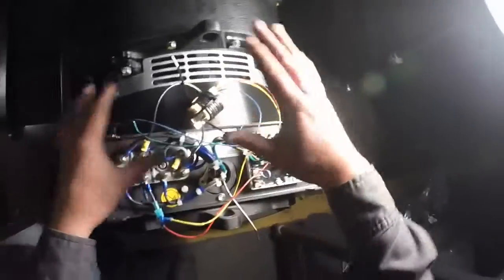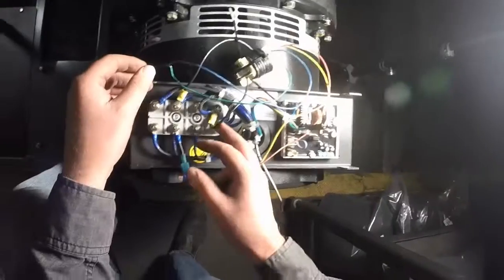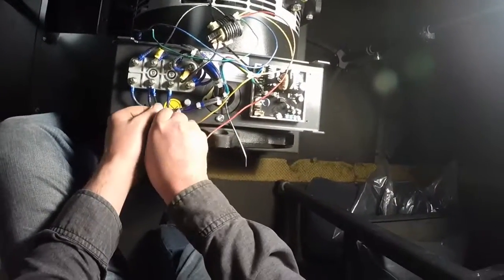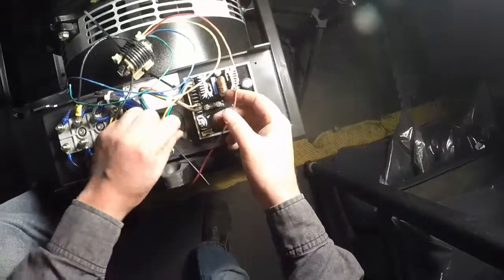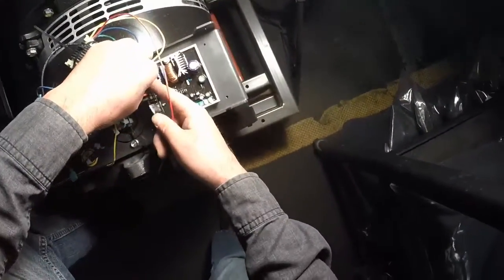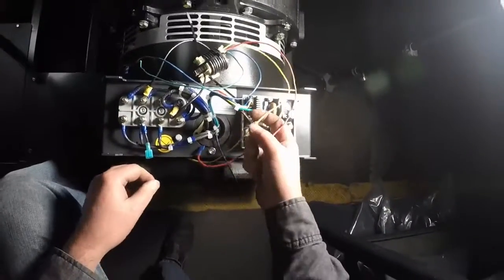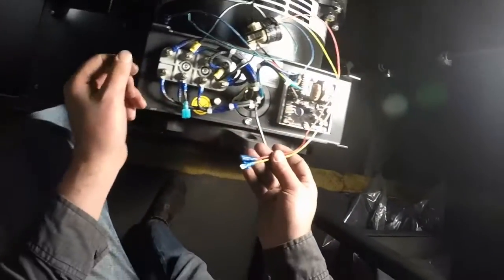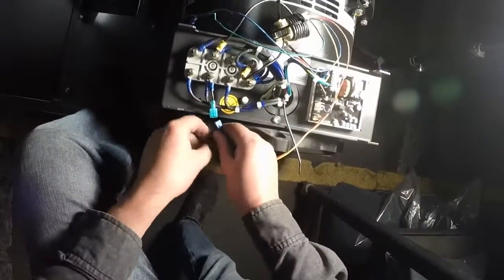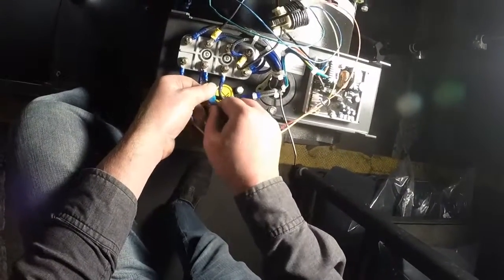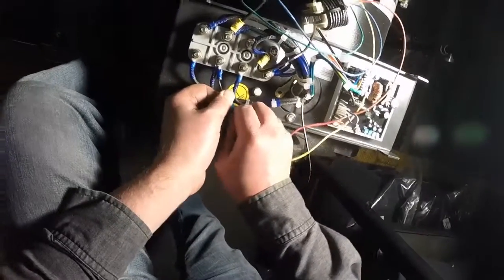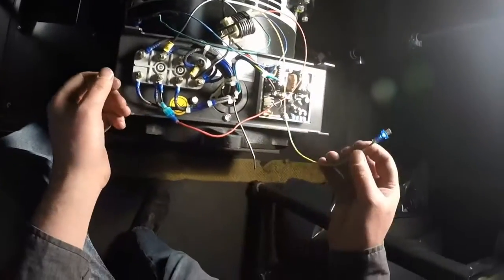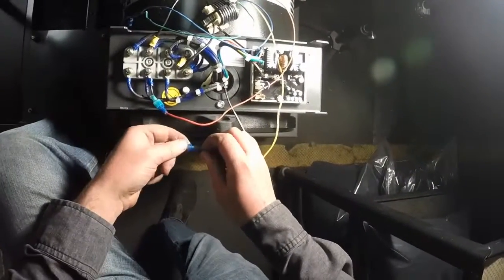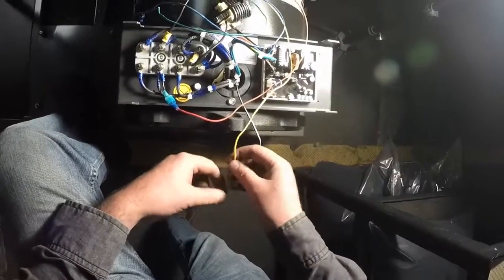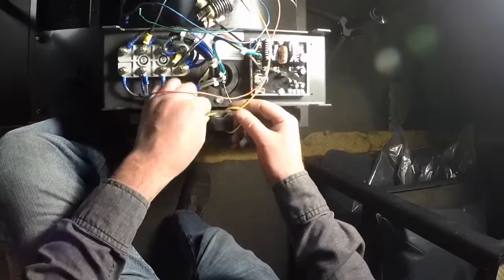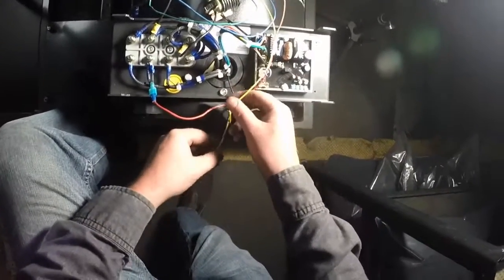So in order to test the polarity of this current transformer, what you should do is connect the wires up, disconnect the current transformer from terminal 6 on the DSR and reconnect the green wire to terminal 6. And then take the current transformers and plug the female terminal into the male terminal that is connected to leg 2 on the generator. And then be very careful, since this output is going to have high voltage on it, so this should be kept in some way that it's not going to touch anything, or you're not going to touch it.